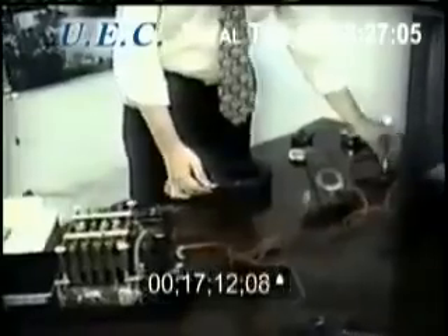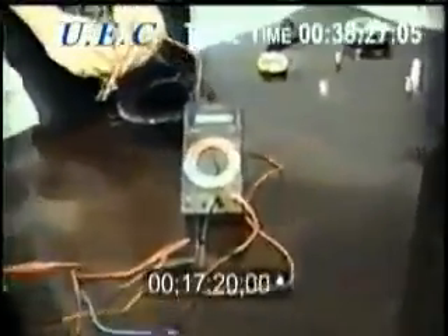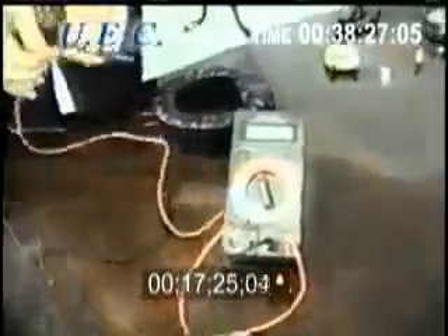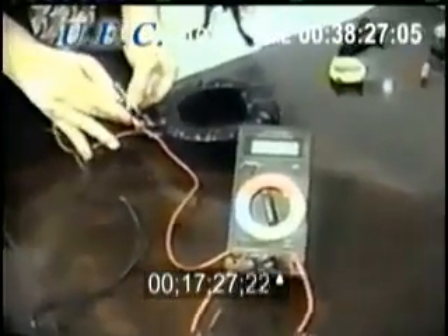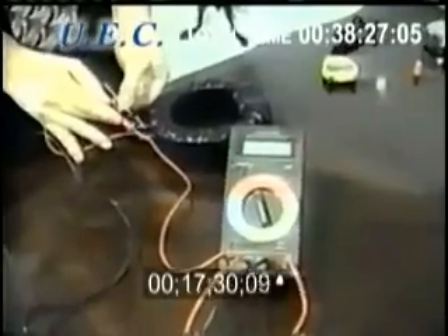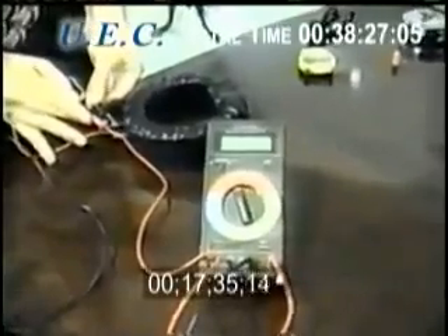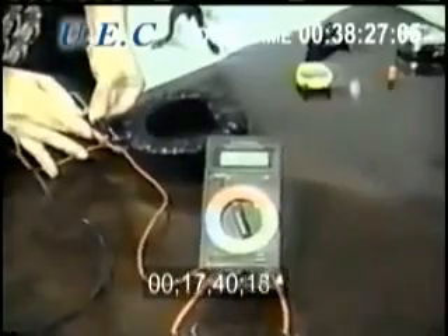I'll show you the output of the device. This is a voltmeter set at 200 volts DC. See both leads here on the voltmeter, connect them directly, and the unit is putting out about 186 volts. Checking... okay, 186 volts. It will fluctuate a little bit, and the unit still vibrates, as have the other units in question.